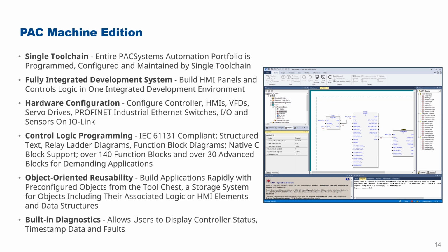Diagnostics includes online logic evaluation status. It includes tooltips on structured text to see current values. It includes being able to have data watches for values, as well as being able to view register tables. And we also have fault tables to control and support diagnostics in the CPU and for the I/O. And there's even a built-in trending tool as well.